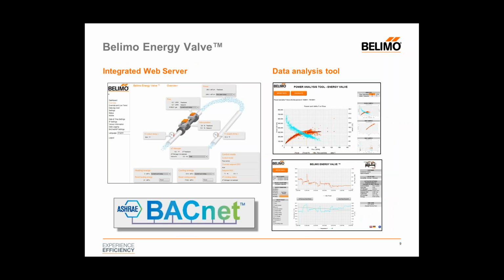One of the other things, as I talked about, is this integrated web server. Now this is a very powerful feature. It can be connected to the valve over a TCP/IP connection to look at what's going on in real time within the valve. This is the image you see on the upper left portion of the screen. We can look at flow, so you can see the actual flow going through the valve at any specific time as the flow changes, decreases, or increases. We can look at the supply and return water temperatures, power, what the Delta T Manager activation is, or if it's not activated. We'll look at heating and cooling energy, just to name a few. So this gives a very powerful way to log into the valve and see in real time, and make changes in real time, of what's going on within the system.